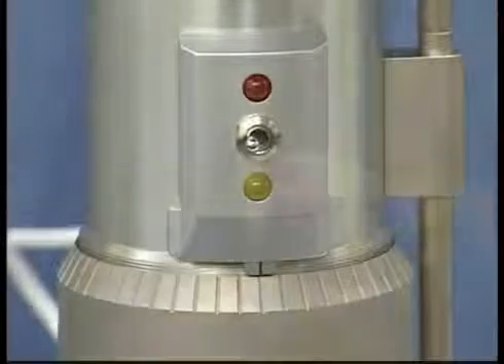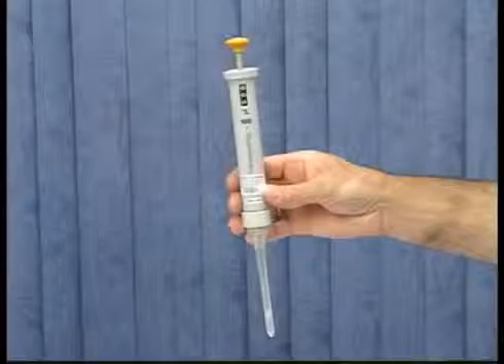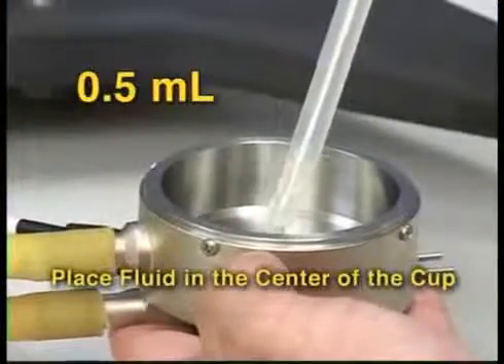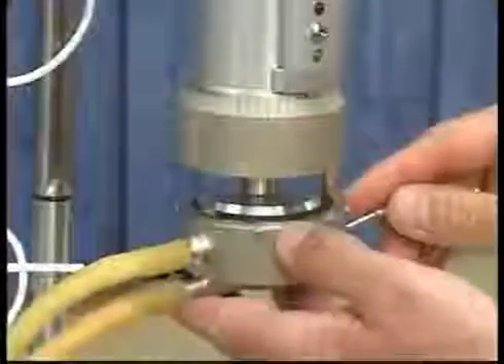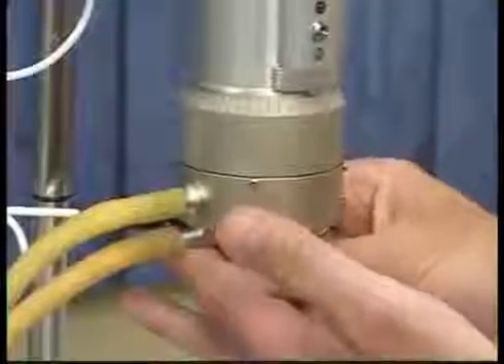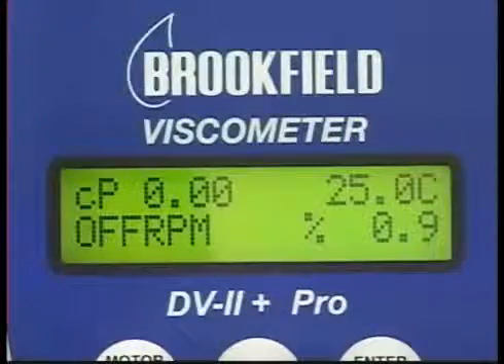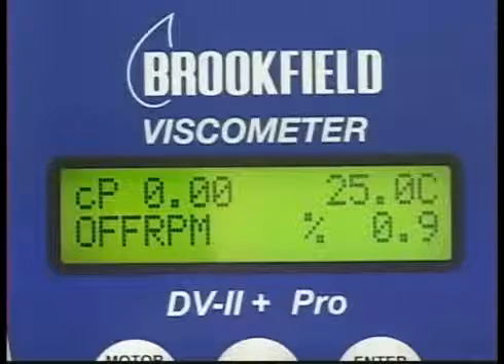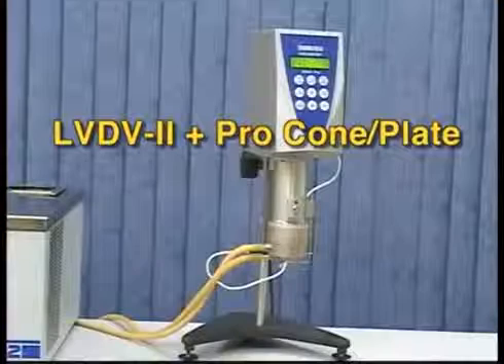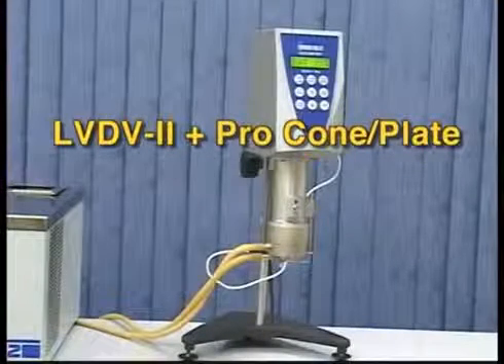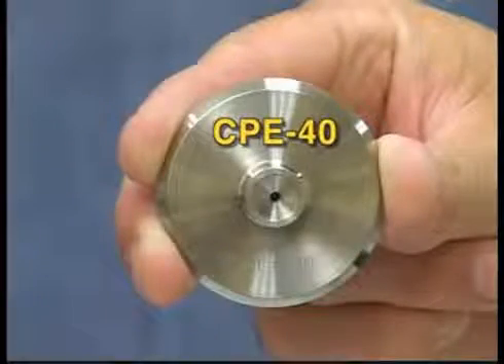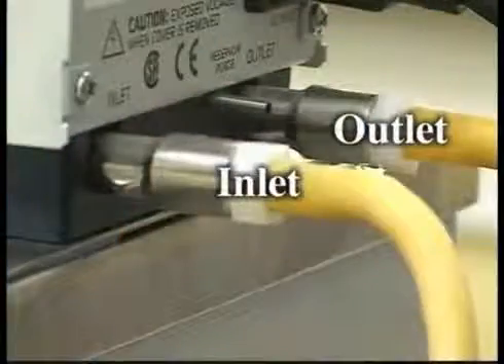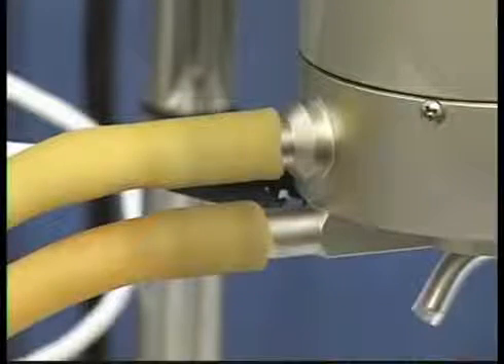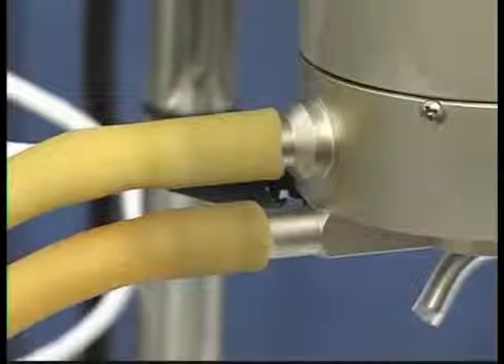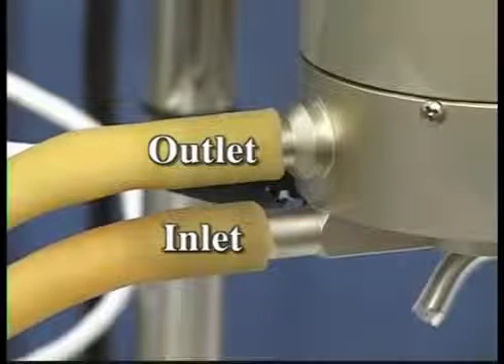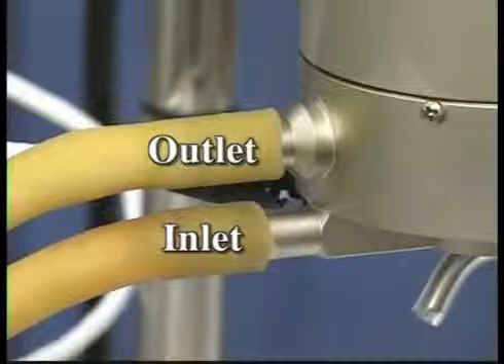With the gap properly set, measure the correct amount of viscosity standard fluid to be used, in this case 0.5 milliliter. The viscosity standard fluid needs to be equilibrated at 25 degrees Celsius to get an accurate reading. In this example, we will be using an LVDV2 Plus Pro cone plate instrument with a CPE 40 cone spindle. Hoses from the water bath inlet and outlet will connect to the corresponding cup's water jacket inlet and outlet for proper circulation. The cup's outlet is the top connection. The inlet is the bottom connection.